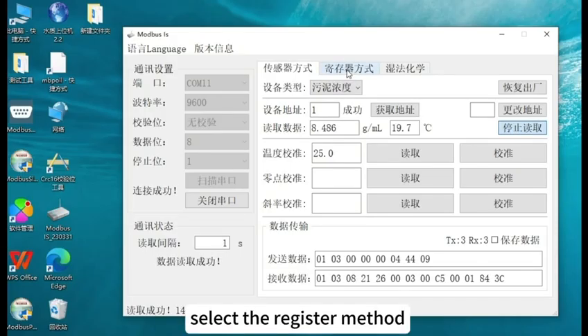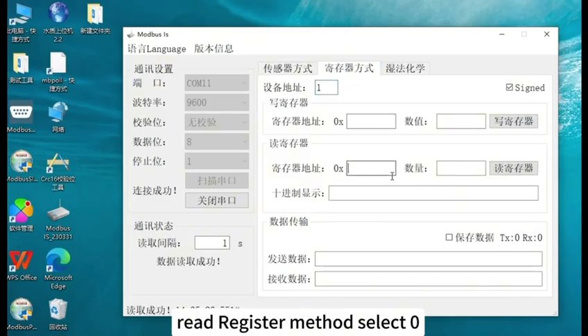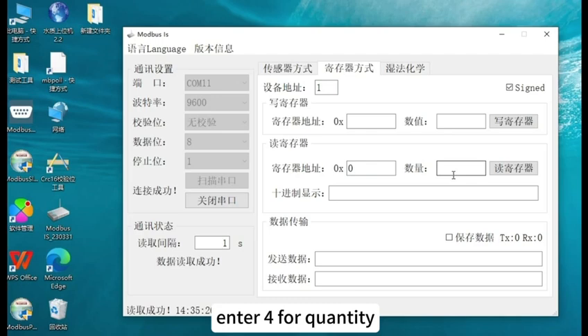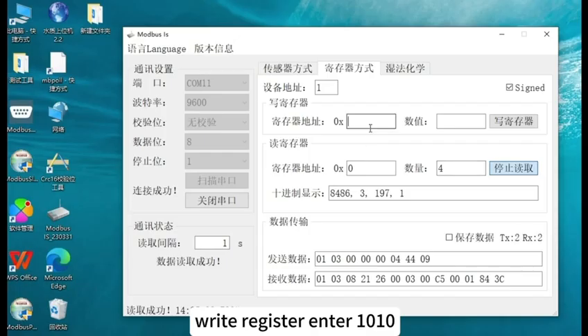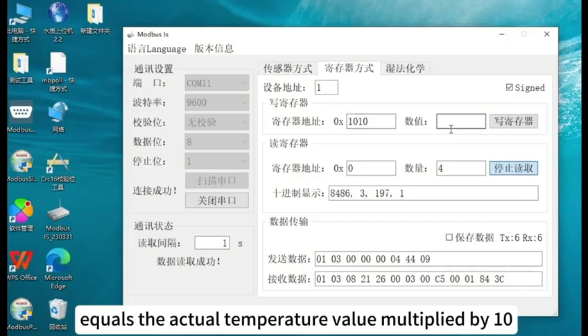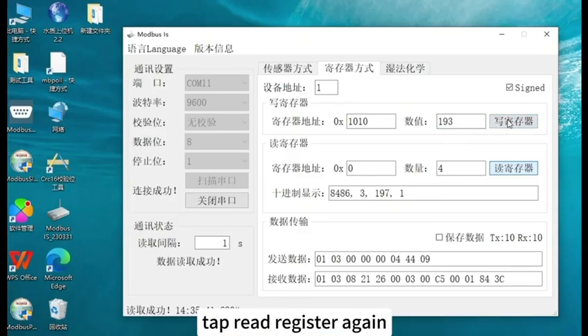Select the register method. Read register method, select 0. Enter 4 for quantity. Click Read Register. Write register, enter 1010. Numeric write value equals the actual temperature value multiplied by 10. Tap Write Register. Tap Read Register again.